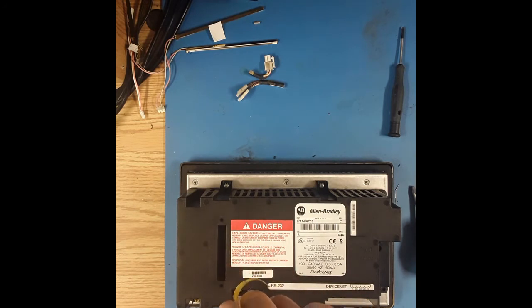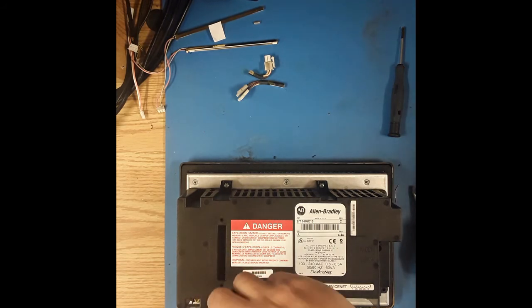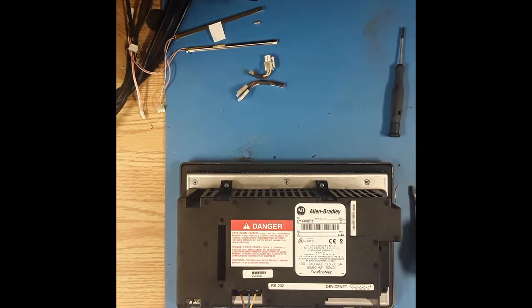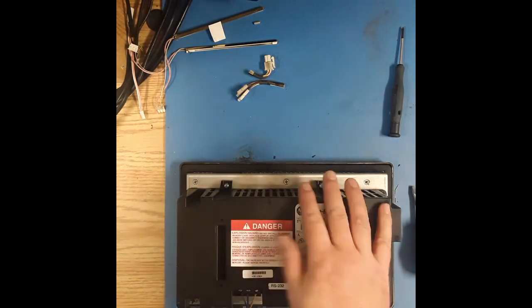So when you're testing this on the bench, just be aware. The ground, that's your green, your yellow-green wire, make sure that's right. The other two wires, for testing, it doesn't really matter. You can interchange them. So you're line and neutral.